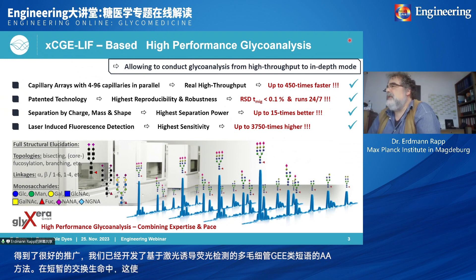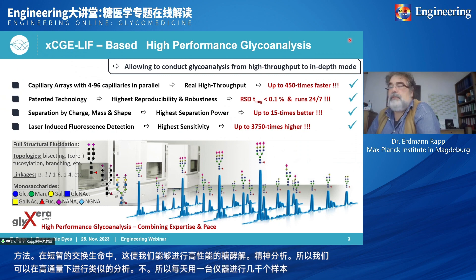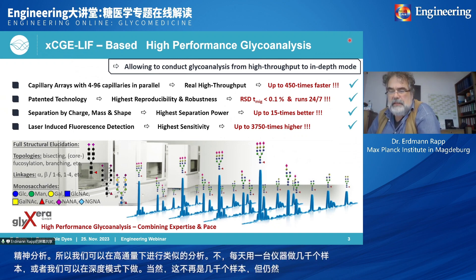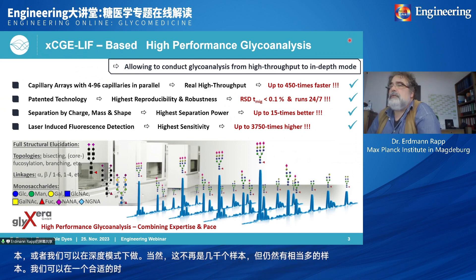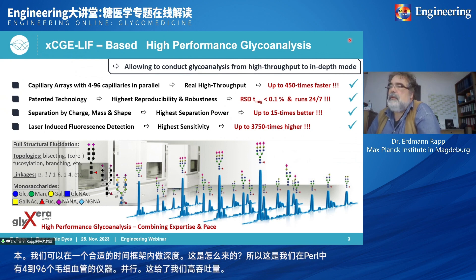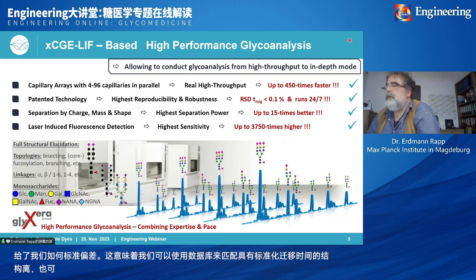We can conduct glycoanalysis in high-throughput mode — several thousand samples per day with one instrument — or in in-depth mode with a decent number of samples in a reasonable timeframe. We have instruments from 4 to 96 capillaries in parallel, giving us high throughput. The patented technology gives us the highest reproducibility and robustness, with very low standard deviations. This means we can use databases for matching structures with normalized migration times, with separation by charge, mass, and also by shape — very high separation power.